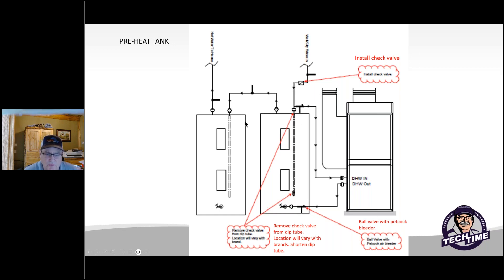Also remember a lot of places have off-peak electric hot water, so you may have two of these that are controlled after hours or at nighttime. A lot of times those tanks may be set at 140 degree water. That is not always conducive to the hot water generator desuperheaters working, because we don't push out that kind of hot water.